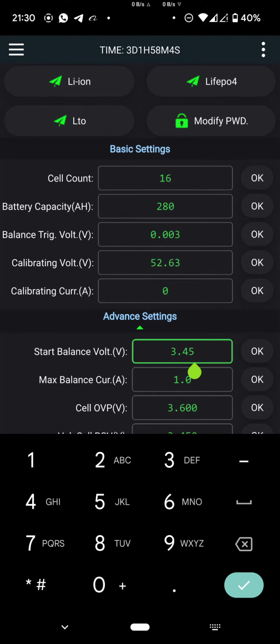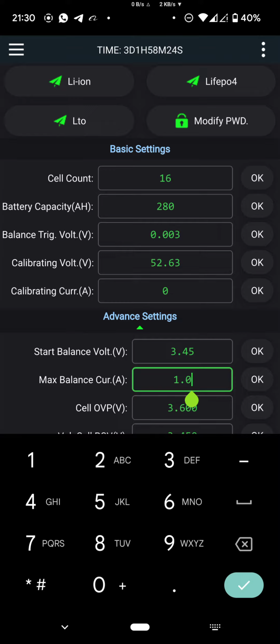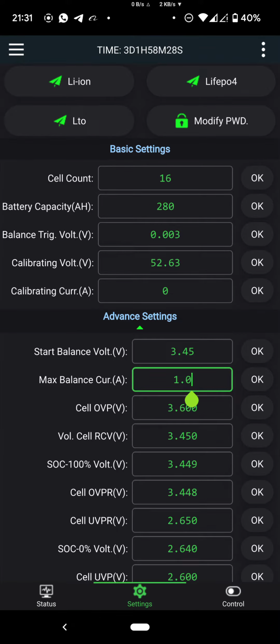So first, the start balancing voltage. I recommend 3.45. So if one cell reaches this voltage, it will start balancing and feed the lowest cell. Max balance current, I don't find the need to change this for 1 amp or 2 amp balancing. So here we have this parameter. It is one of the new parameters. RCV, it's the requested voltage by the BMS from the charger. So the BMS requests this voltage from the charger, this value times 16, and I recommend to set it also to 3.45, the same as the start balance voltage.